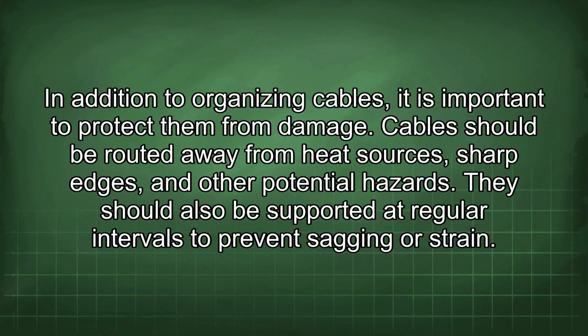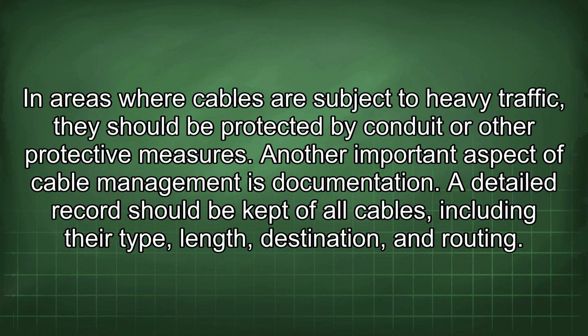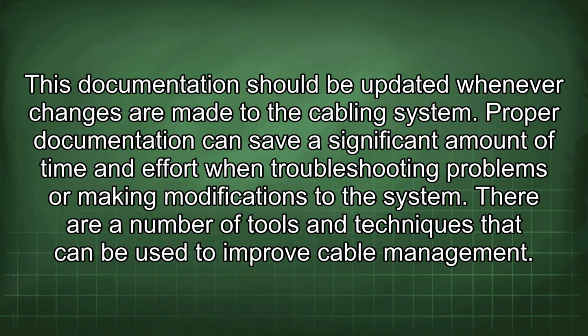In addition to organizing cables, it is important to protect them from damage. Cables should be routed away from heat sources, sharp edges, and other potential hazards. They should also be supported at regular intervals to prevent sagging or strain. In areas where cables are subject to heavy traffic, they should be protected by conduit or other protective measures. Another important aspect of cable management is documentation. A detailed record should be kept of all cables, including their type, length, destination, and routing. This documentation should be updated whenever changes are made to the cabling system. Proper documentation can save a significant amount of time and effort when troubleshooting problems or making modifications to the system.